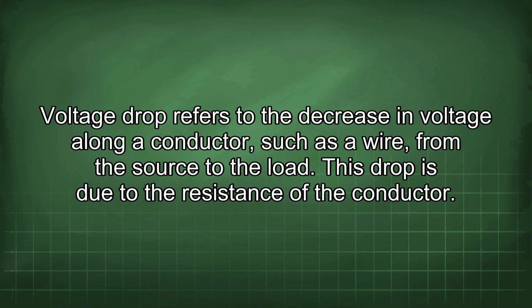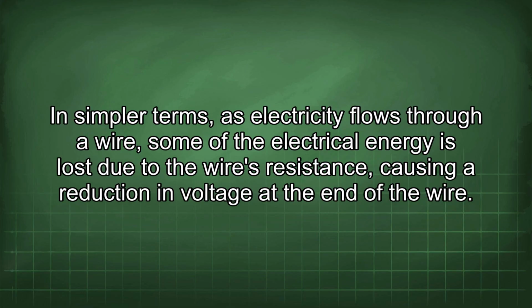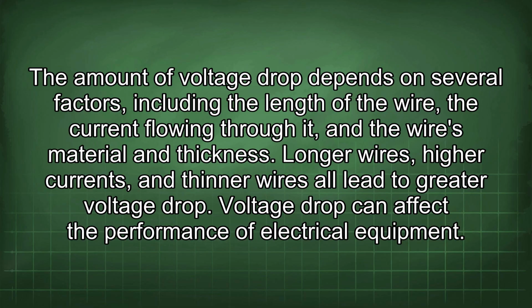Voltage drop refers to the decrease in voltage along a conductor, such as a wire, from the source to the load. This drop is due to the resistance of the conductor. In simpler terms, as electricity flows through a wire, some of the electrical energy is lost due to the wire's resistance, causing a reduction in voltage at the end of the wire. The amount of voltage drop depends on several factors, including the length of the wire, the current flowing through it, and the wire's material and thickness. Longer wires, higher currents, and thinner wires all lead to greater voltage drop.